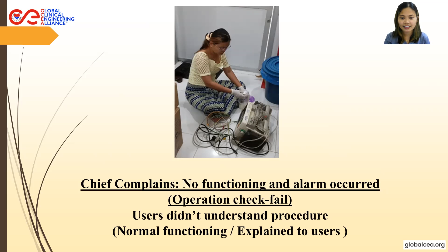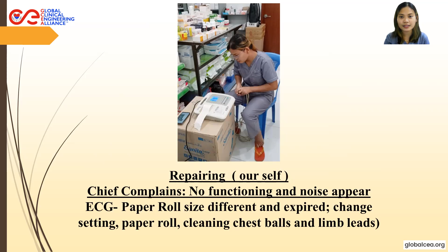Next slide, please. Repaired by our staff. This photo shows cleaning of an ECG machine, and the complaint is that it is not functioning and noise appears. The paper roll size was different and the paper roll had expired. So I changed the paper roll and the setting, and then cleaned the chest balls and limb leads. After that, the ECG machine is functioning well. Next slide, please.